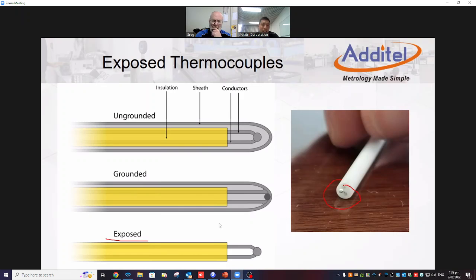So if you're testing a mixture of noble metal and base metal, or using the noble metal as a reference to test the base metal, the base metal thermocouples may have some contamination outside of the probe. If you have a really high temperature test, you can easily imagine that the contamination will transfer from the base metal probe to the tip of the thermocouple, because the tip of the thermocouple is exposed. And then the noble metal thermocouple will have a pretty huge error. That means you cannot use it anymore.